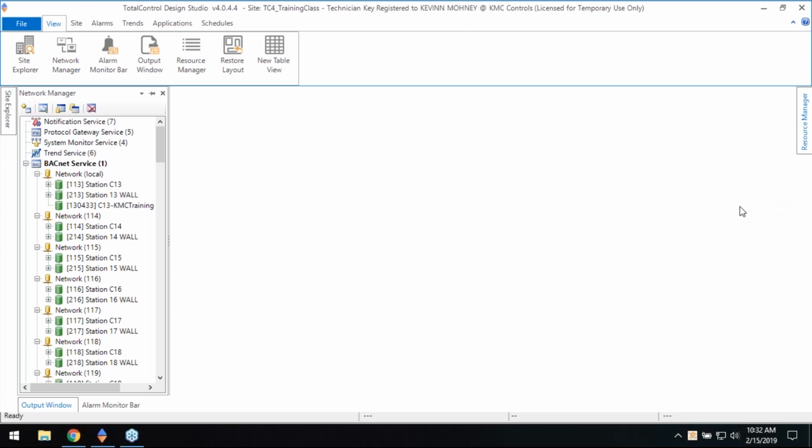First thing I'm going to do is assume that you used Connect or TotalControl to create a job with the application wizard and deployed that job on the existing network. If you're going to use TotalControl as the front end or the BMS, then I would wait to do trends, schedules, and alarms till TotalControl's up on the site, but it would be okay to deploy and configure controllers with Connect. Schedules, trends, and alarms are all database driven things, so they really need the database to make them work so you can see them on the web.